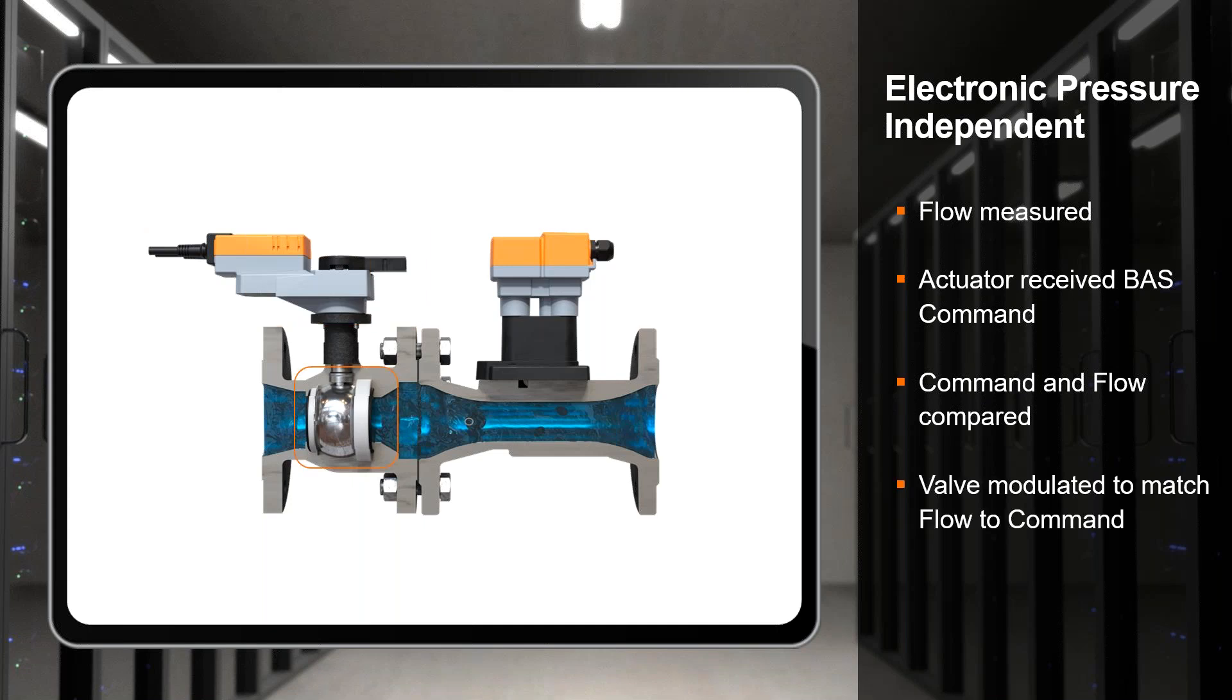We're going to measure the liquid flow rate with an ultrasonic flow sensor. Then we're going to use the actuator to receive a control signal from the automation system and compare that to the flow value that's currently being measured. Then the actuator can decide whether to modulate the valve or not based on whether we're at the correct flow, below or above. If the automation system sends a 50% command to the control valve, 50% for the way this control valve is programmed is 45 gallons a minute. It will look at the flow meter's flow rate. If it's above 45 gallons a minute, it will modulate the valve more closed until it gets to 45 gallons a minute and then stay there.